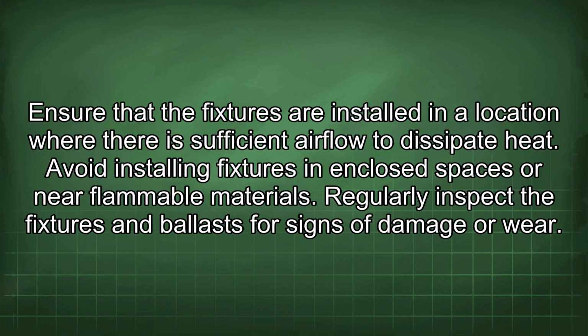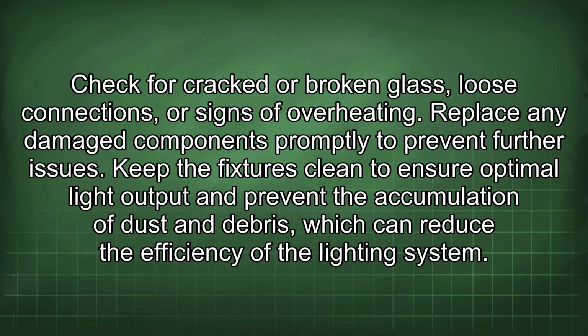Regularly inspect the fixtures and ballasts for signs of damage or wear. Check for cracked or broken glass, loose connections, or signs of overheating. Replace any damaged components promptly to prevent further issues. Keep the fixtures clean to ensure optimal light output and prevent the accumulation of dust and debris, which can reduce the efficiency of the lighting system.